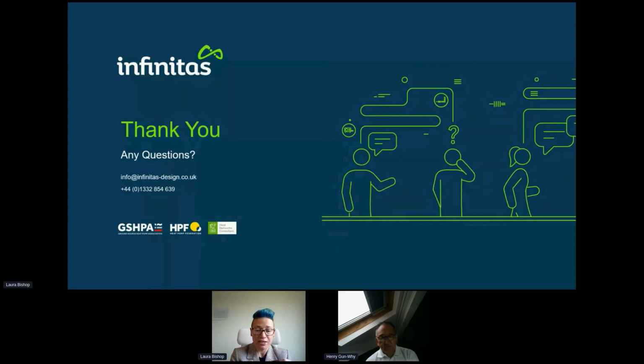Fifth generation is the cold loop side. That's where, as I said before, you might drill down boreholes and then circulate that water from the boreholes around a network, and each building has its own heat pump. The benefit is that if you've got an older building that needs slightly higher temperatures, that can have one particular type of heat pump. If you've got another building that's brand new and needs low temperatures, you can have a different heat pump.